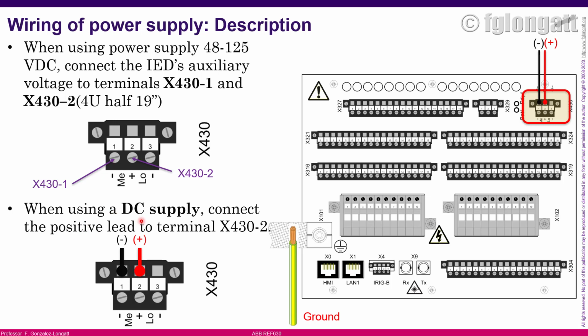Because we are using direct current, polarity is so important, and we need to define which terminal is positive and negative. According to the installation manual, section 5, the terminal X430-2, here in the middle, is the connection point for the positive terminal. Here we use positive in red color and negative in black color, just for your basic understanding about the polarity. Polarity in the IED is extremely important.